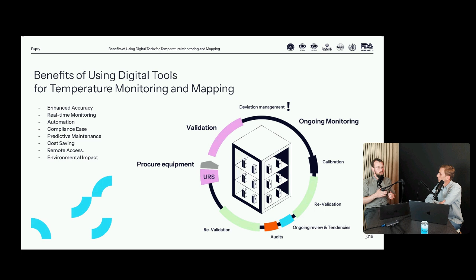It does not work for door opening studies. That's really important to remember, because then we have spikes of temperature, and it's really dependent on how much time after that you take the temperatures. But for door opening studies specifically, what we normally do with each of our customers is define what is an acceptable return rate or return time. So yes, you will get an outlier if you open the door, but for how long can we accept this?